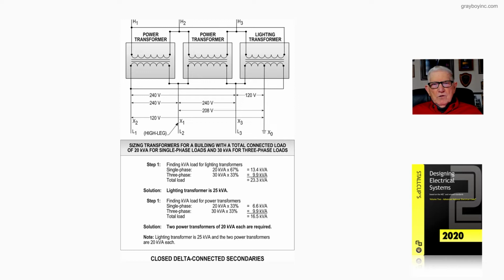Go to your connection again, L2, and you go through 240 volt, right around to 120 volt to ground, X0. Now, electricians like to use more sophisticated calculations. They say, okay, we have a 240 volt winding in the power transformer 2. We have a 120 volt winding connected to earth ground in the lighting transformer. So add 240 volt to 120 volt, divide that by the square root of 3, 1.732, you come up with 208 volt.